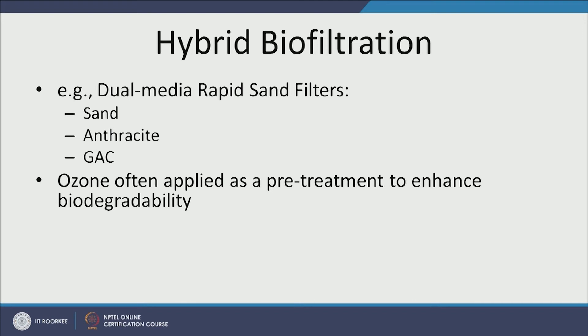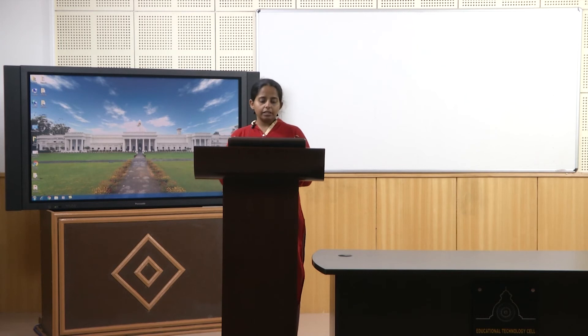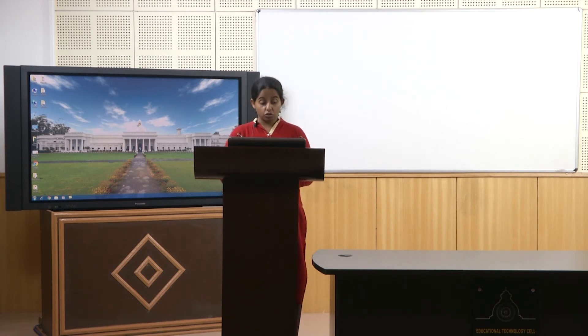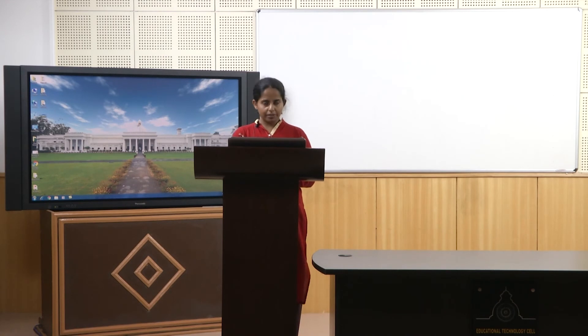Hybrid biofiltration uses a dual media rapid sand filter with sand and anthracite or GAC (activated charcoal), often with ozone as a pretreatment to degrade NOM and enhance biodegradability before passing through the filter. This approach is applicable when biodegradable organic matter is low — less than 1 mg BODL per litre. If BOM is high, such as during rainy season when NOM is elevated, it will cause significant head loss in the rapid sand filter, making biofilm pretreatment a better option.